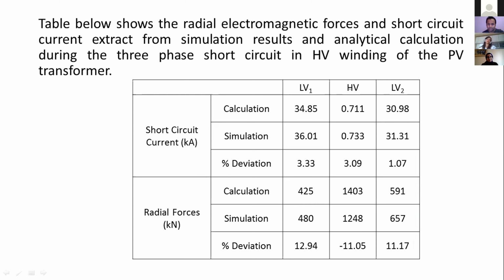For the high voltage winding, the short circuit current is calculated at about 0.7 kiloampere, and the simulation results show a value of about 0.7 kiloampere, and the deviation between the simulation and analytical is less than 5%, or about 3%. For the low voltage winding, the short circuit current is calculated at about 30 kiloampere, and from the simulation result about 31 kiloampere, and the deviation between these values is about 1%.